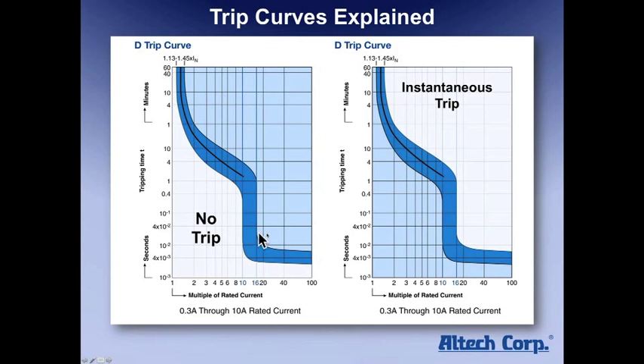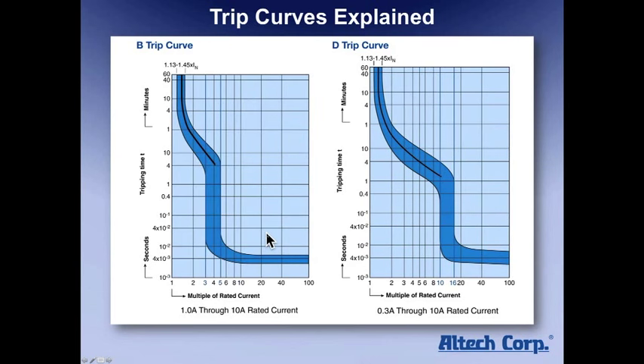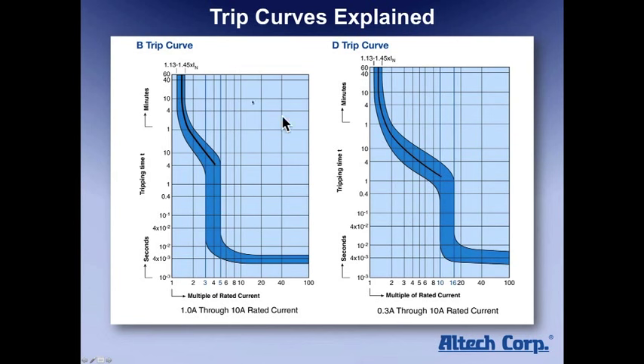The D-trip curve is more or less for motors, allowing that area for the motor startup so you won't have nuisance tripping.